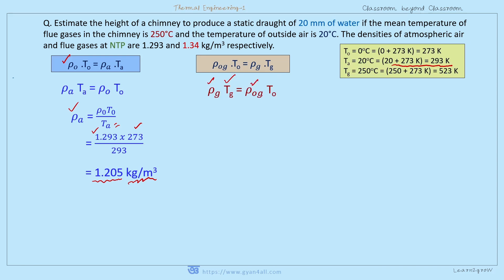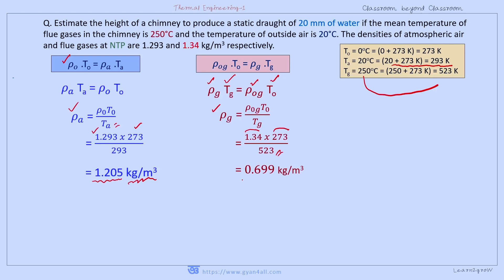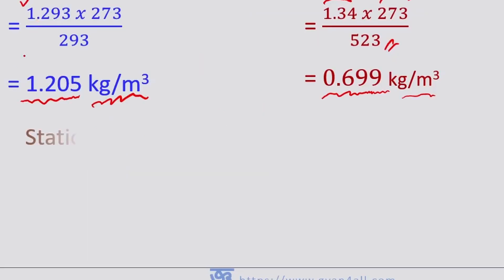Similarly, using ρ_G·T_G = ρ₀_G·T₀, we solve for ρ_G — the density of flue gas at 250°C. Substituting: ρ₀_G = 1.34 kg/m³, T₀ = 273 K, T_G = 523 K. Doing the calculation gives ρ_G = 0.699 kg/m³.